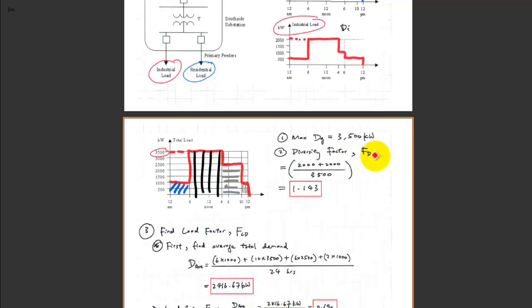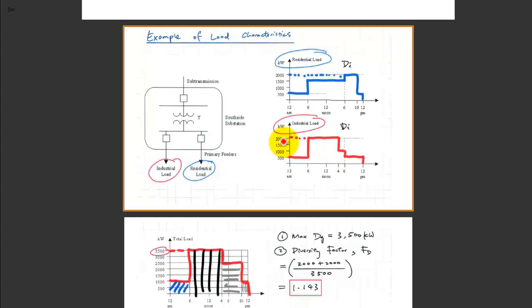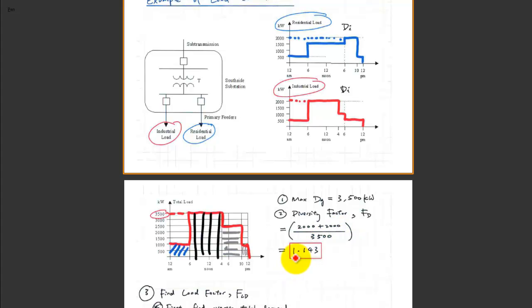The F sub D definition is the sum of all individual loads, which is the non-coincidental demand. The individual maximum value for the blue curve is 2000 kilowatts and for the red curve is 2000 kilowatts. So you sum both individually for the numerator — 2000 plus 2000 — and the denominator is the maximum coincidental demand, which is 3500. The diversity factor is therefore 4000 divided by 3500, giving you 1.143.